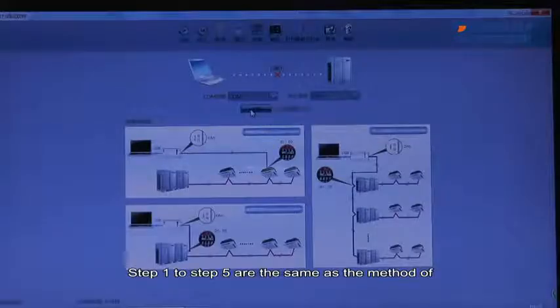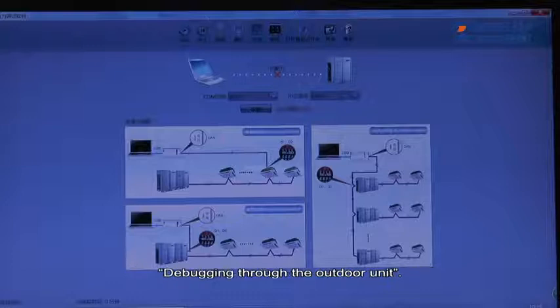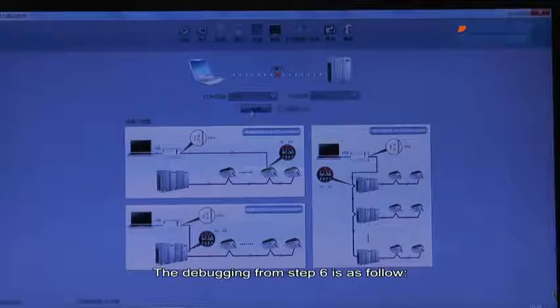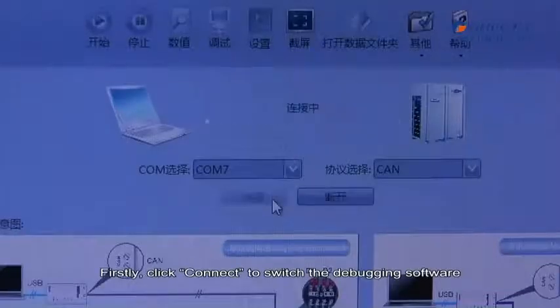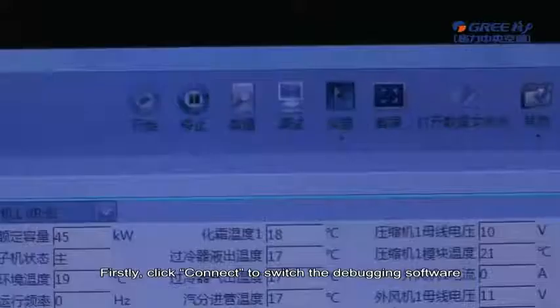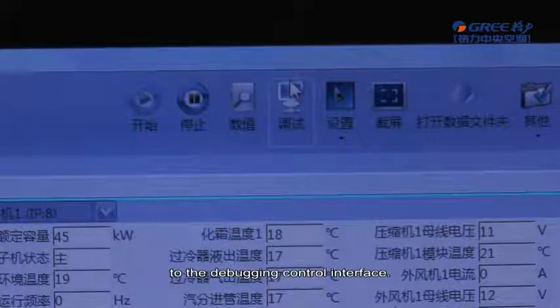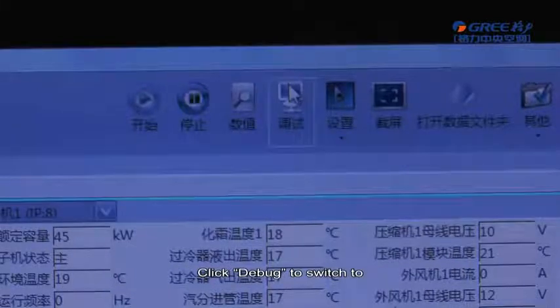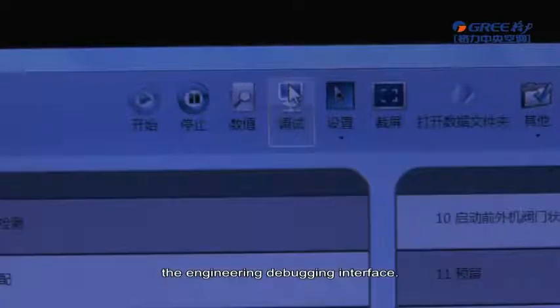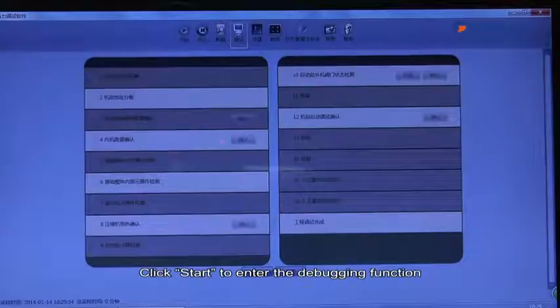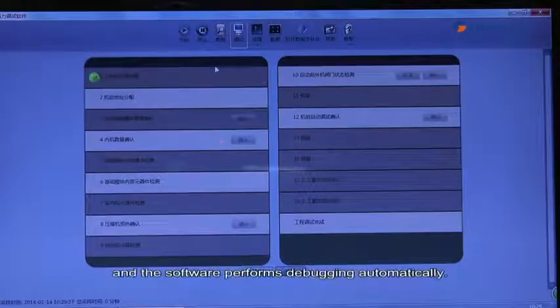Debugging process. Step 1 to Step 5 are the same as the method of debugging through the outdoor unit. The debugging from Step 6 is as follows. Firstly, click Connect to switch the debugging software to the debugging control interface. Click Debug to switch to the engineering debugging interface. Click Start to enter the debugging function, and the software performs debugging automatically.